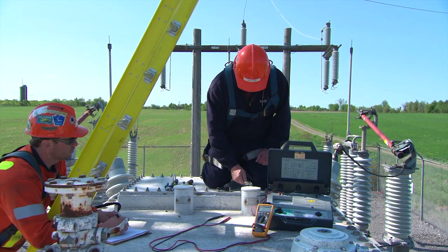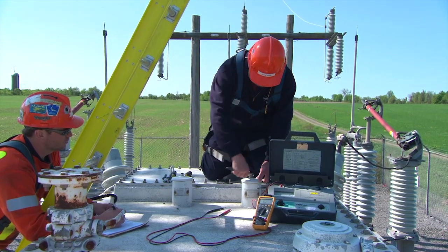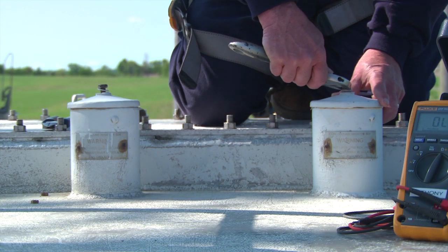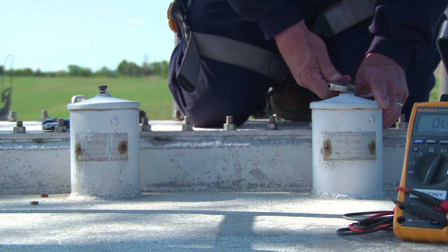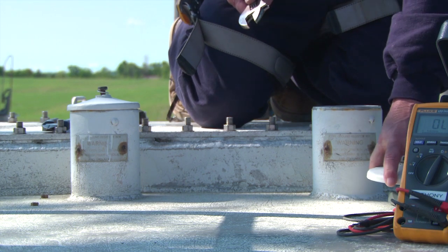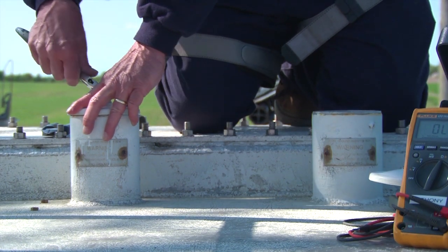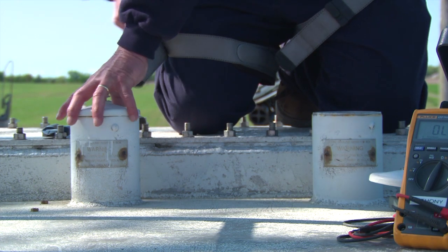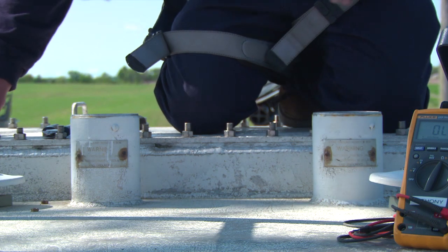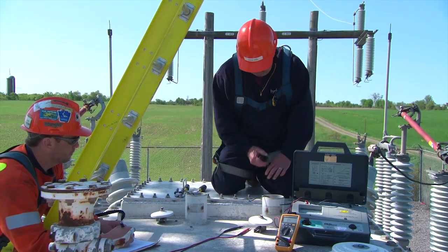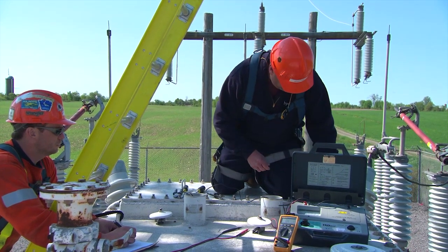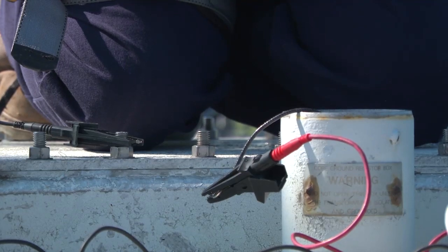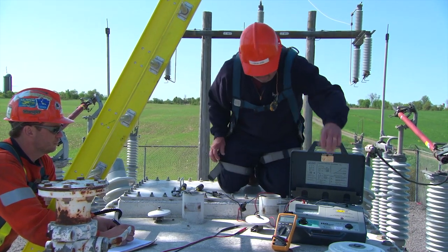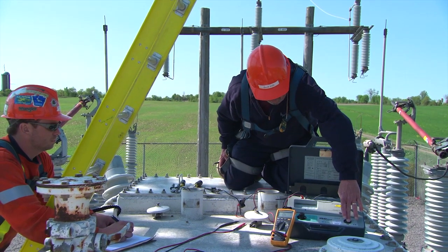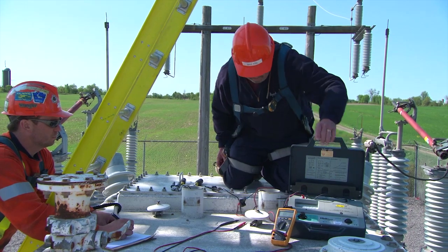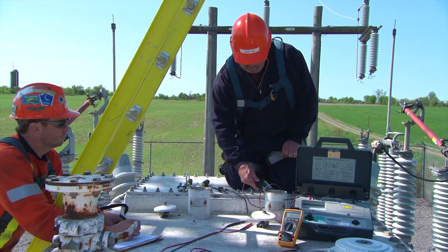Expose and disconnect core ground connectors from the main transformer core and the auxiliary transformer core. Use a digital multimeter to check the core grounds resistors. Test core grounds at 1000 volts for 1 minute. Measure and record the core ground resistance and record the transformer ambient temperature. Any reading of less than 100 megaohms must be reported to Maintenance Technical Services.